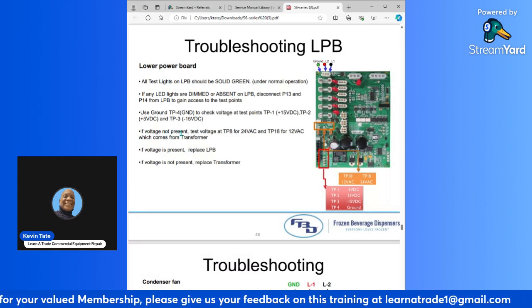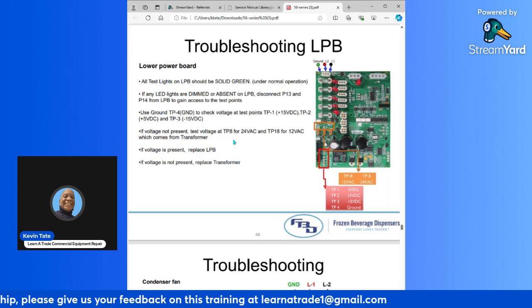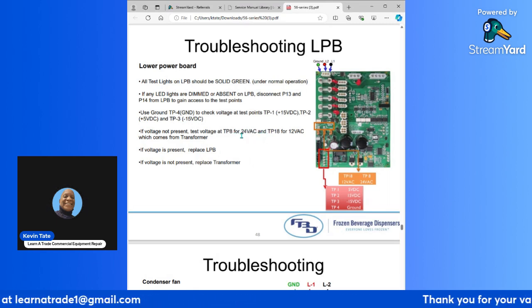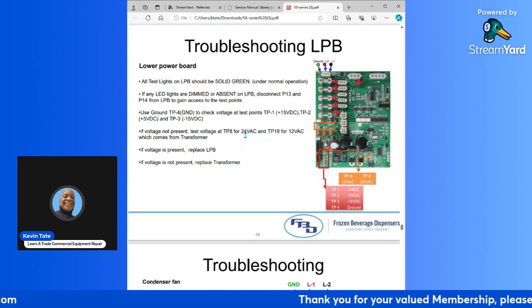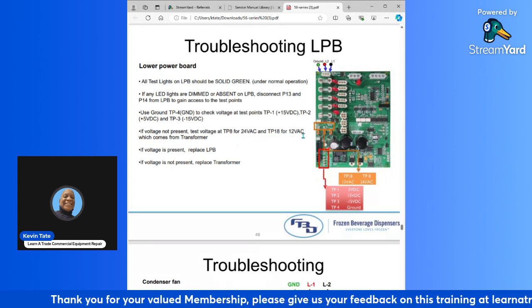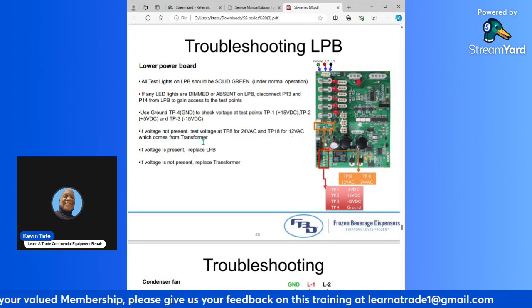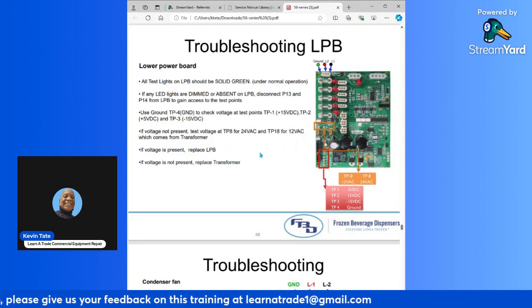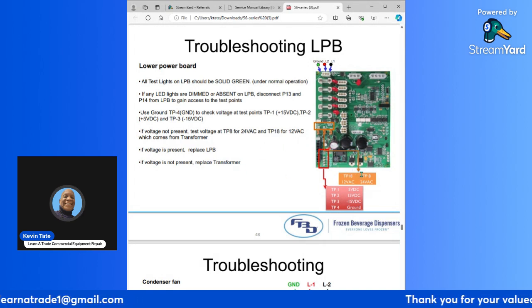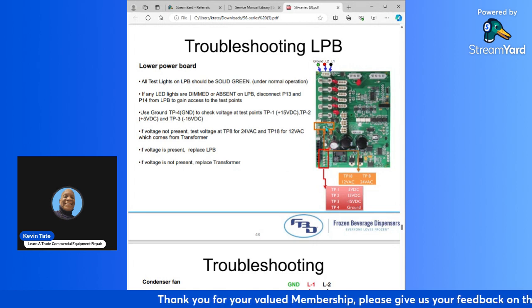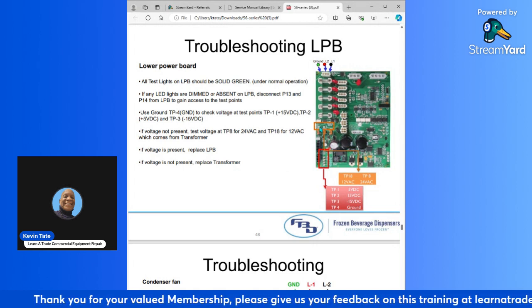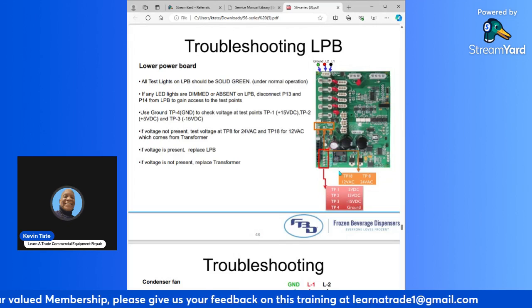If voltage is not present, test voltage at TP8 for 24 volts DC. AC. You would test point 8 for 24 volts AC, and test point 18 for 12 volts AC, which come from the transformer. This is your TP18, and this is your TP8 test points right here. This is where you would test those out.